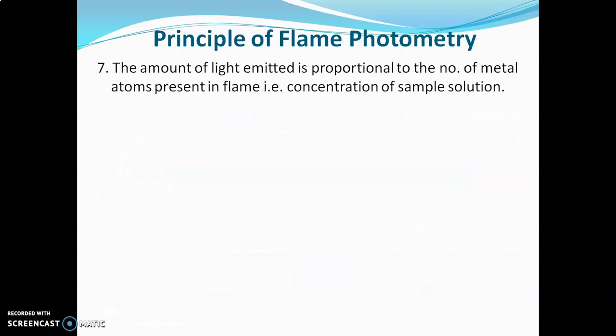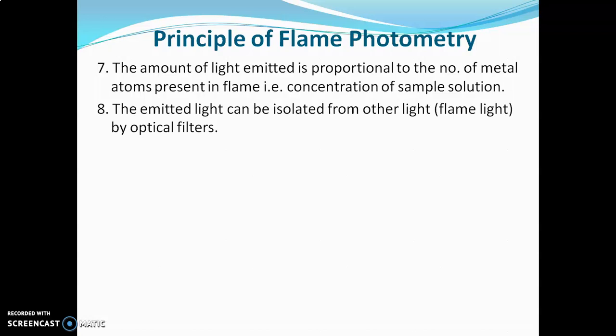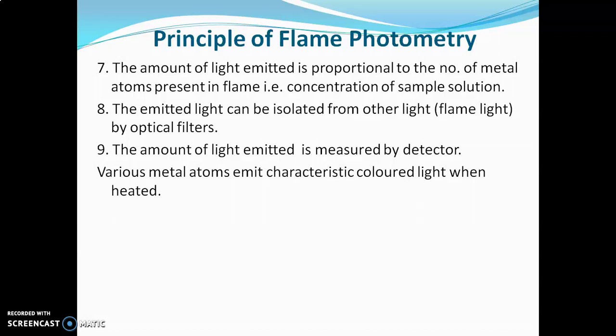The amount of light emitted is proportional to the number of metal atoms present in the flame, which means the amount of emitted light is directly proportional to the concentration of the metal atom in the sample solution. The emitted light can be isolated from other light — such as the flame background — using optical filters or monochromators. The amount of light emitted is then measured by a detector.